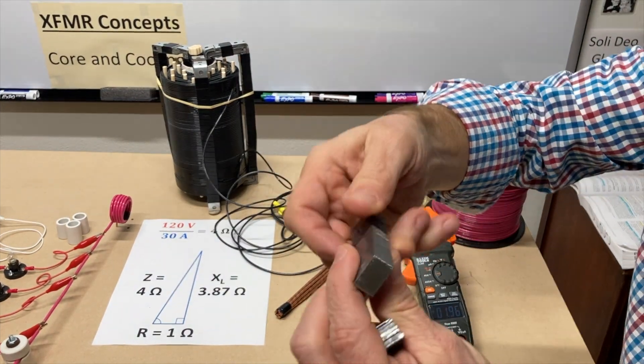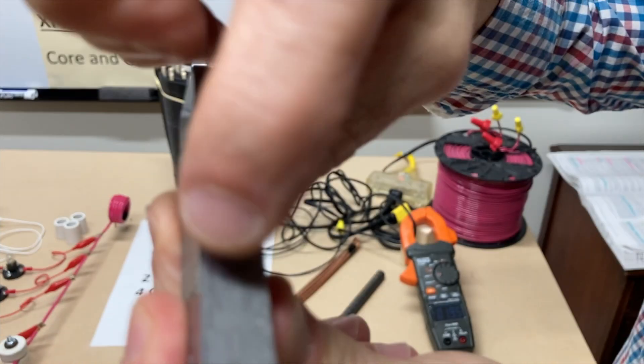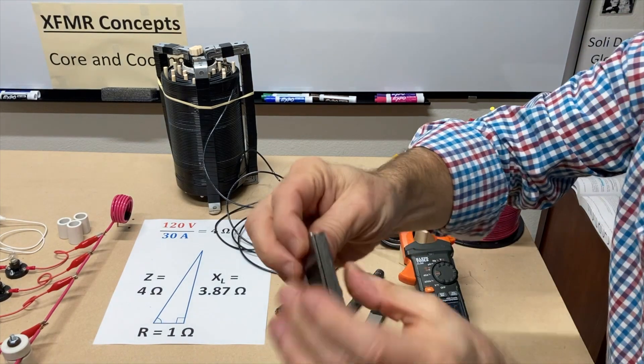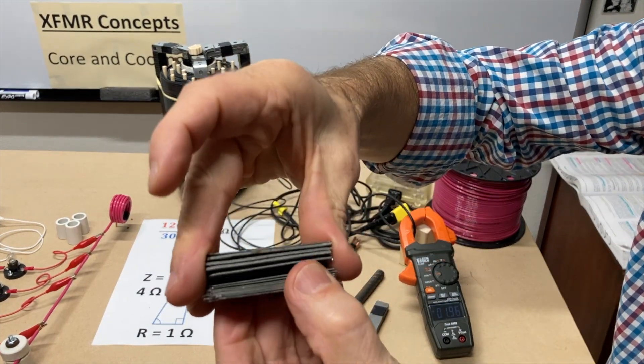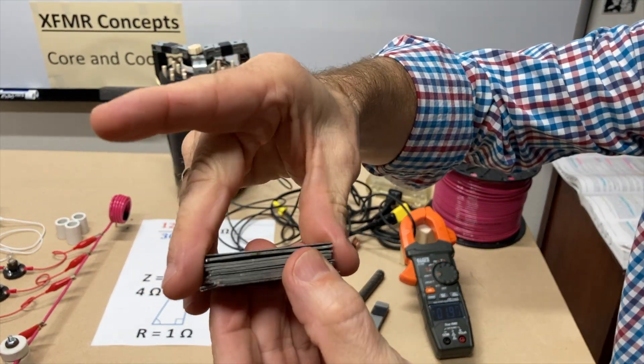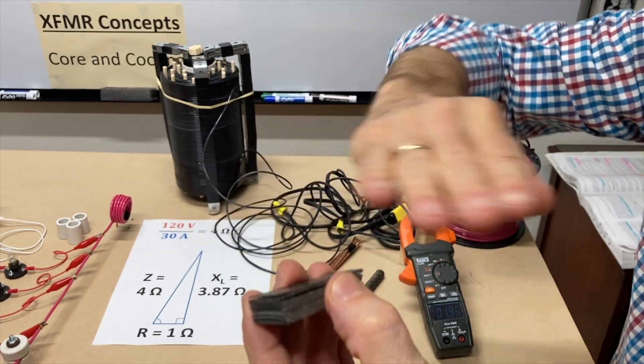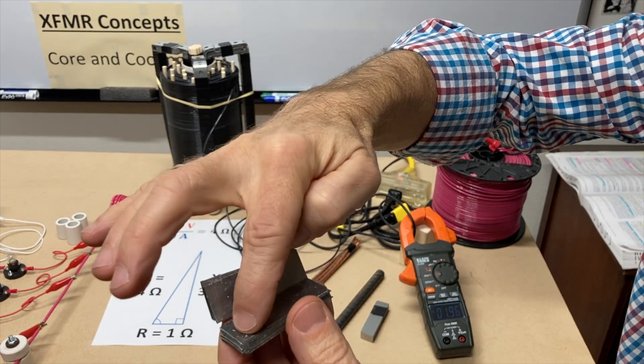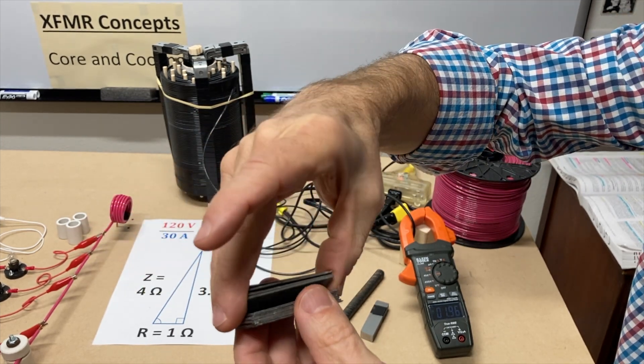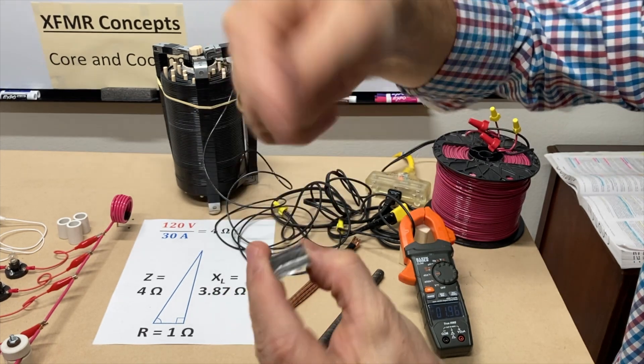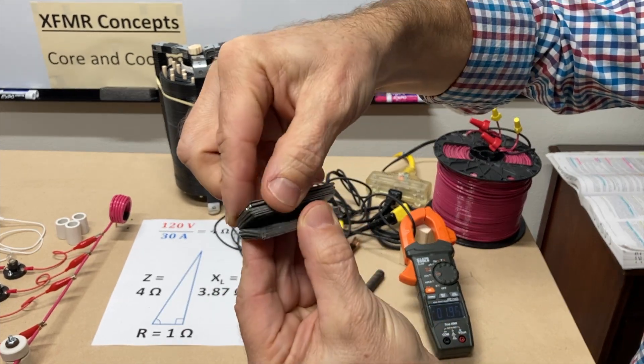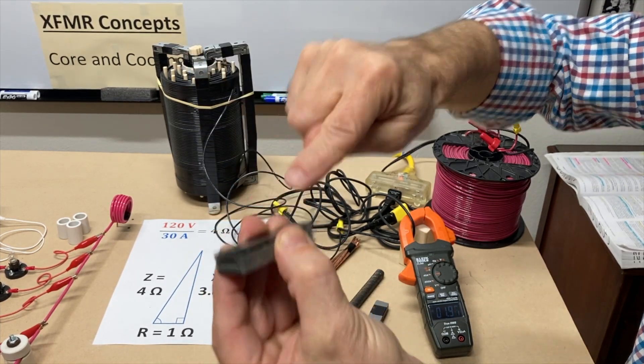And here's a section of what that looked like. I don't know if you can see all these individual little strips on there. I got some here that I took apart, right? It's all these little layers. And what we call them is laminations, kind of like layers of laminated wood. And what's interesting is each layer is coated with an insulating material to isolate or insulate each lamination from the next. So the eddy currents cannot flow this way.